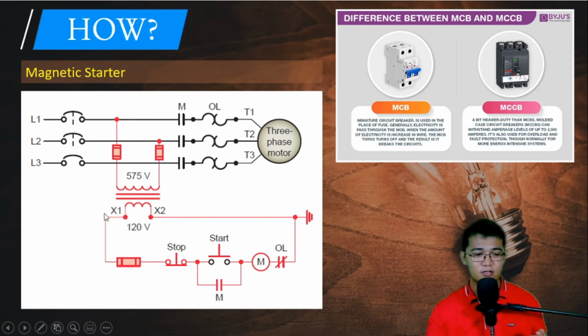Then after that, on the control circuit, we have another fuse, a stop push button normally closed, then a start push button normally open, then the coil of our contactor. We know this is the coil of our contactor because of the designation M. If you notice here, the main contacts are designated M, meaning these contacts will depend on whether this coil is energized or not, whether there is current flowing through the coil or not. And this is the overload auxiliary contact. Once the overload heaters trip, something happens to this normally closed contact, it opens.